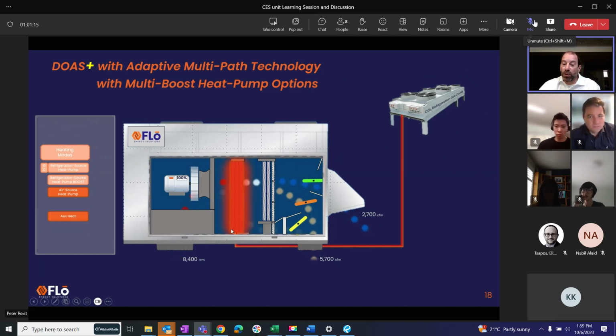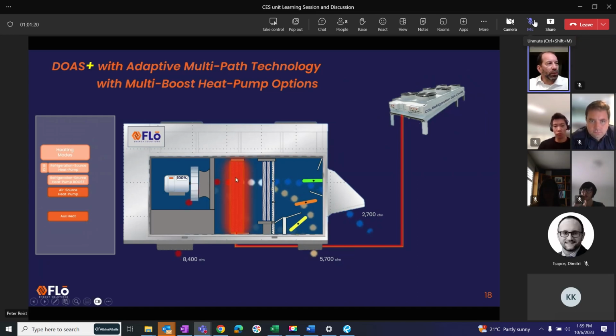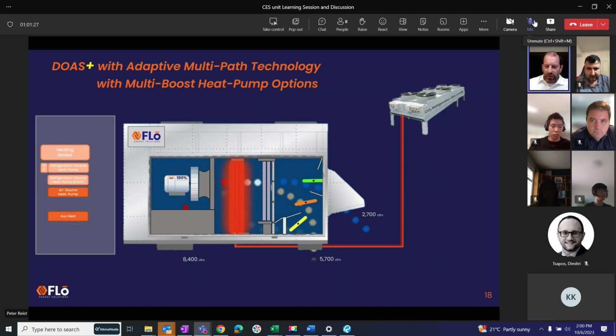When you have a CO2 system, and I know you don't for this project, but other projects when you do, we call this refrigeration source heat pump boost. We can get an enormous amount of heat. Just to give you a sense, the heat you'll get out of your HFC rack, or synthetic refrigeration rack, versus when we do this approach - it takes a different refrigerant, so it's not an option for you right now - but we get 5 or 6 times more heat out of it. So when you guys are working with Dave on some of the CO2 projects, just know that we get an enormous amount of heat out of refrigeration systems when it's a CO2 system.